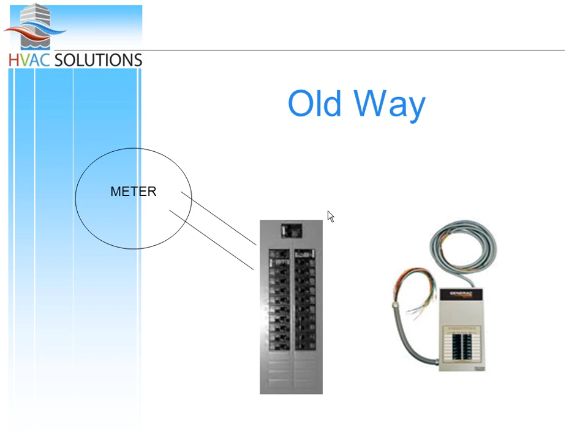So then I would say, what is difficult about doing it the old way? Well, the first thing that's difficult is that you have to choose what 16 circuits you want to power. And that might take an hour. It might take a little bit longer than that to figure out what 16 circuits the homeowner wants to have on when the power is off. The other small problem with this is that if you have 16 circuits, that's a minimum of 32 wires that you have to connect. So it's an awful lot of wiring. Plus, they give you a 30-foot whip. So if you're only 5 feet away from the circuit breaker panel, you have to cut that down and redo it anyway.